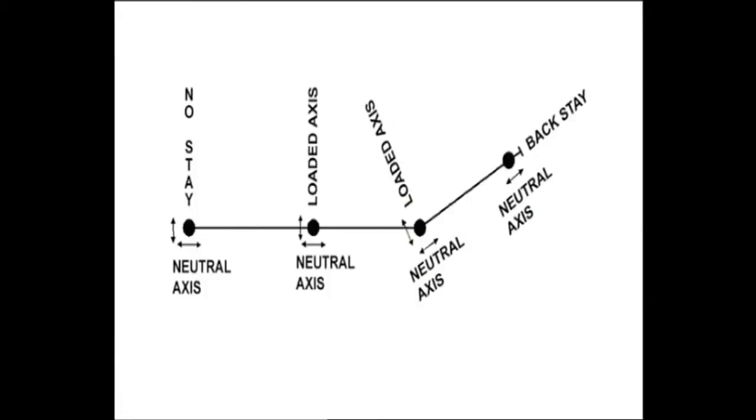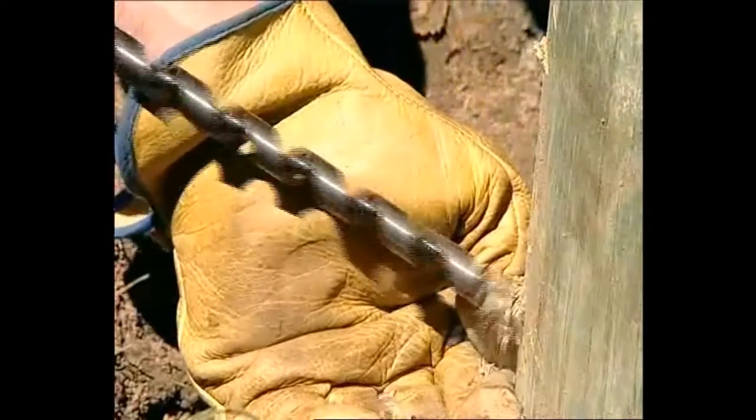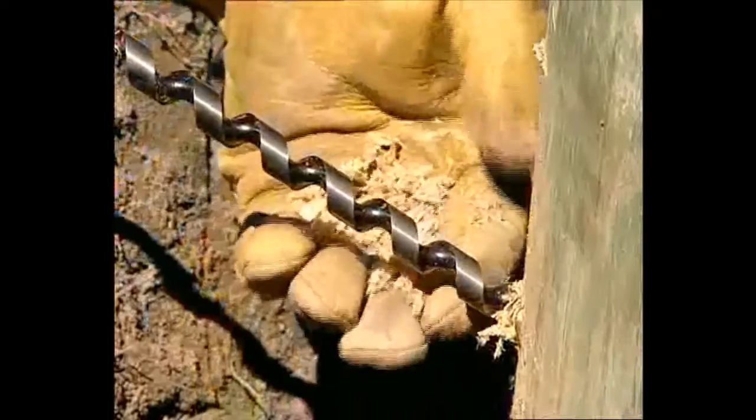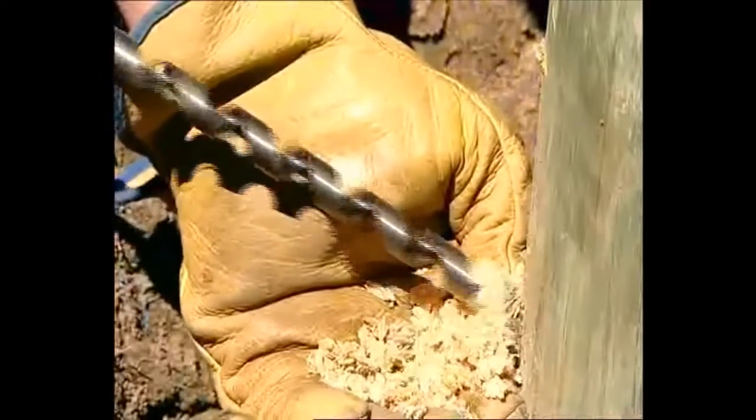Drilling in the other axis at 90 degrees to the conductors will provide a better understanding of wood in the critical zone of the pole. But too many inspection holes here could eventually weaken the pole. Drilling is best done slowly, where the inspector can feel resistance to drilling, hear the crunching sound of the wood, and carefully examine the shavings as they are being removed by the auger.